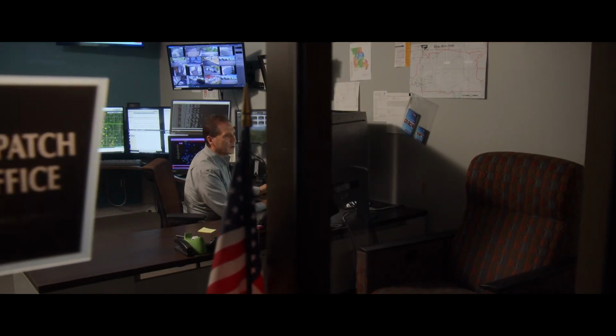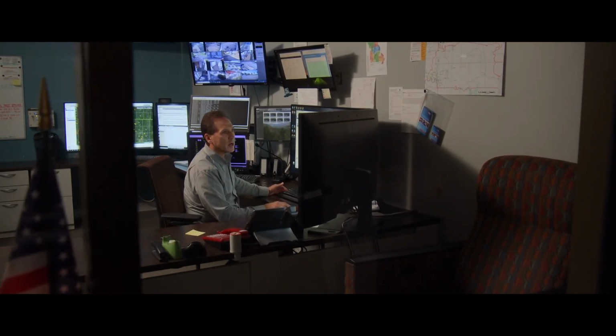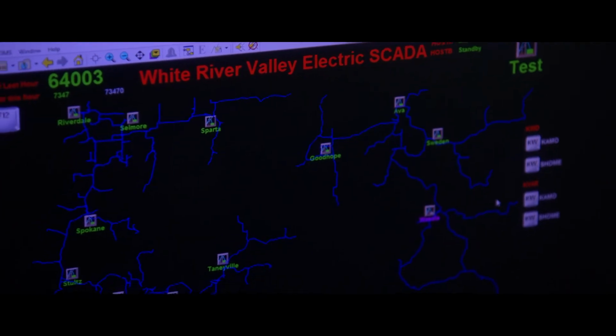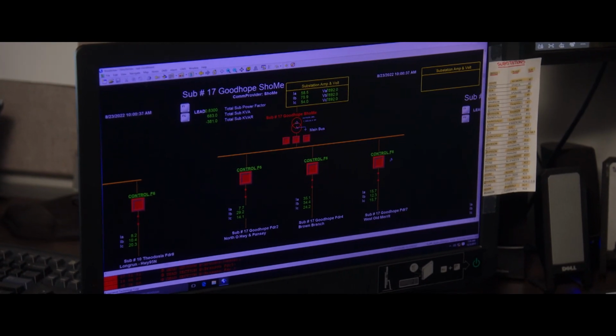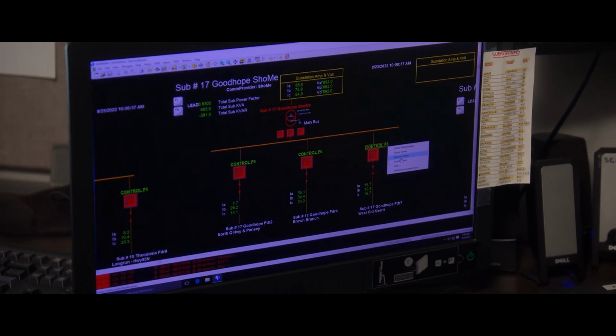Sure. So like Mark was saying, he was talking about blinks, which are faults. I take that information from our SCADA, then I take that sub and that feeder and put it into another program that goes out and reads all the meters on that sub and feeder through our AMR system. As the information comes back, or doesn't come back, the ones that don't come back reading are generally the ones that are out. From there, that's where I can build an outage.